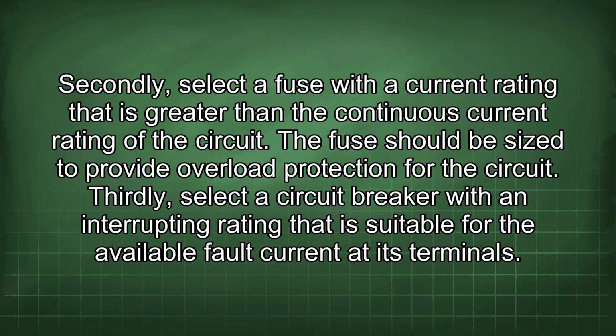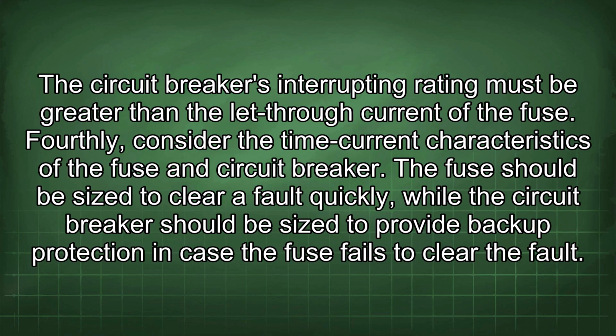The fuse should be sized to provide overload protection for the circuit. Thirdly, select a circuit breaker with an interrupting rating that is suitable for the available fault current at its terminals. The circuit breaker's interrupting rating must be greater than the let-through current of the fuse. Fourthly, consider the time current characteristics of the fuse and circuit breaker. The fuse should be sized to clear a fault quickly, while the circuit breaker should be sized to provide backup protection in case the fuse fails to clear the fault.